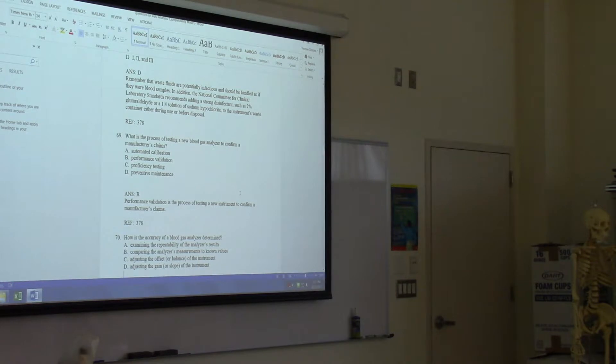How is the accuracy of a blood gas analyzer determined? Examine the repeatability of the analyzer's results, compare the analyzer's measurements to known values, adjust the offset or balance of the instrument, or adjust the gain or slope of the instrument. Okay, compare the analyzer's measurements to known values.